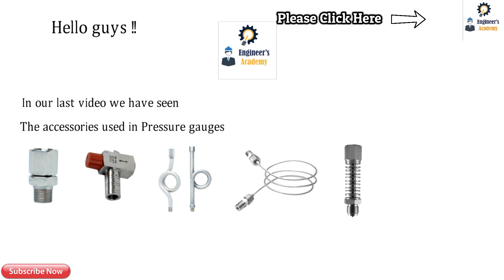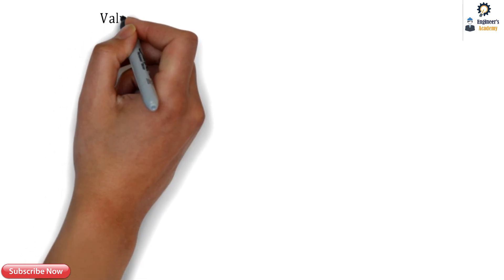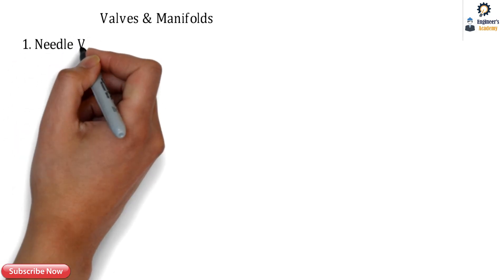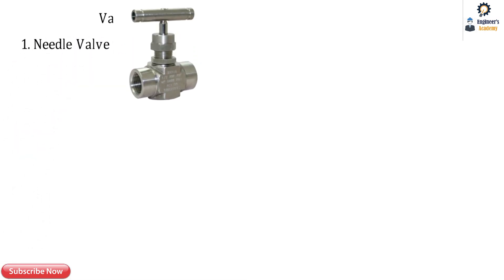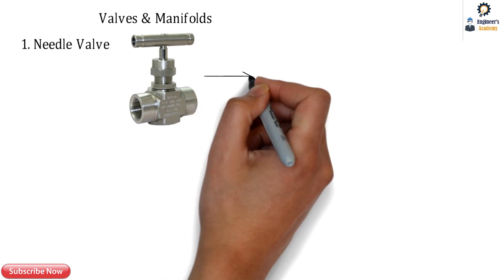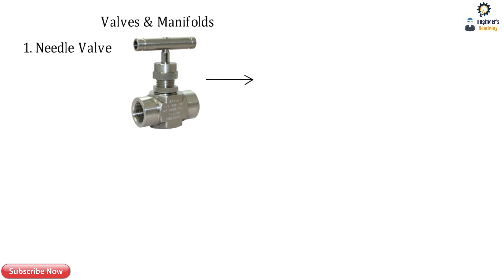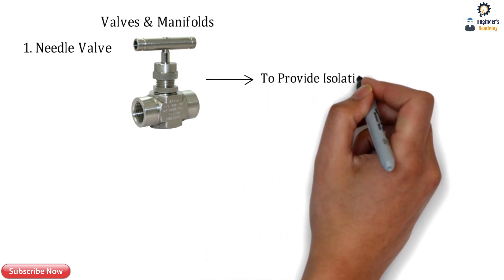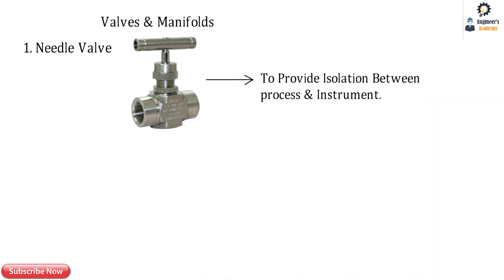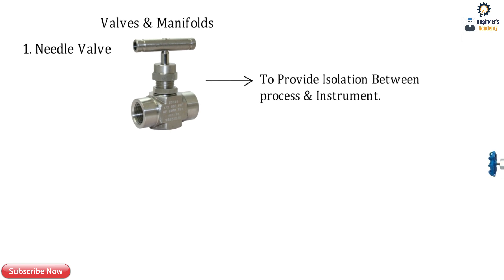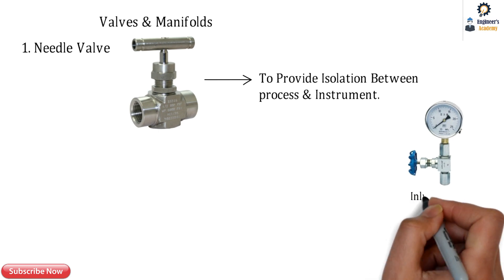Today's topic is the types of valves and manifolds used in the field of instrumentation, specifically those used along with pressure gauges and pressure transmitters. The first one is the needle valve, which is very commonly used in instrumentation and process lines. The basic function of the needle valve is to provide isolation between the process and the instrument. Here, a pressure gauge is mounted on the needle valve with an inline connection.